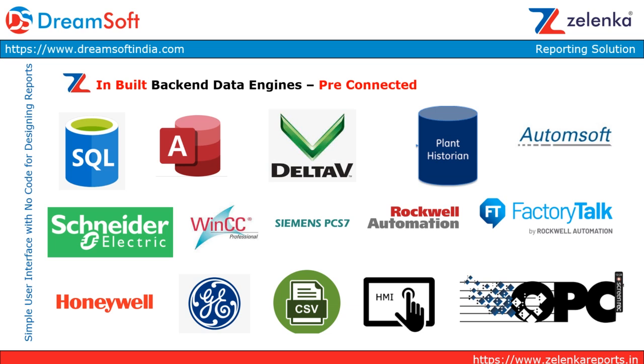CSV files and HMI - if your HMI generates CSV files with data periodically and saves them in a particular location, we can read those files, bring them to a location, and dump the data into a localized database to create reports. Similarly, if your HMI has FTP facility, we can connect via FTP protocol, bring the data, save it into a localized database, and create reports. This data bring-in happens periodically, appending the database over time.